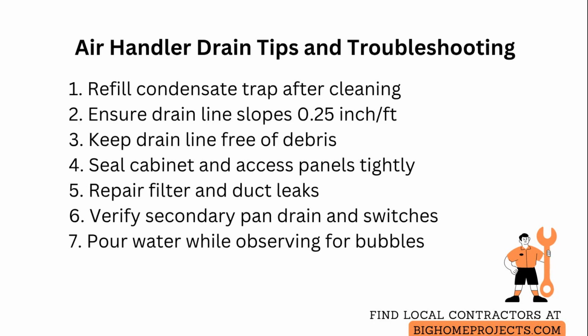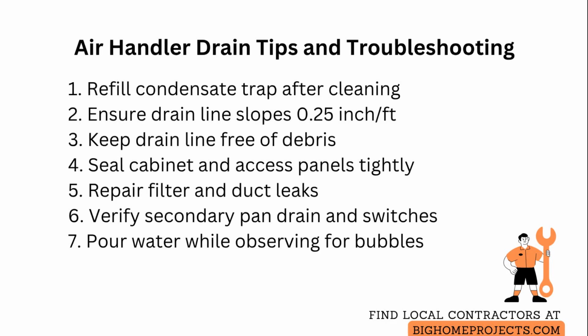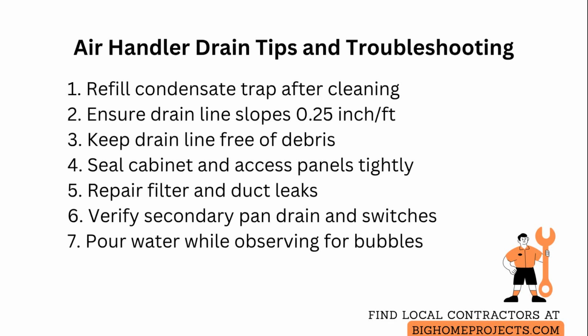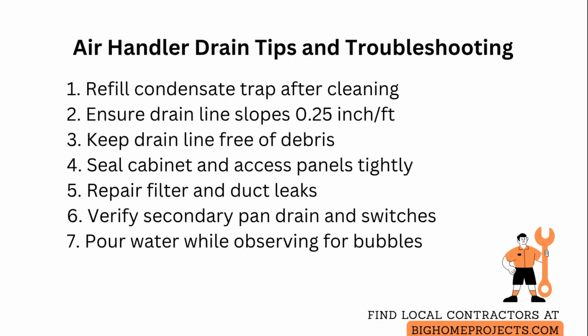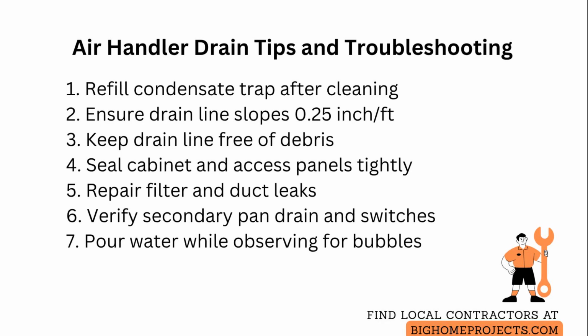Confirm the air handler, cabinet, and access panel seat tightly and that any filter or duct leaks are repaired, because uncontrolled air paths change internal pressures and encourage siphoning through the trap. If a secondary drain pan is present, make sure its drain is unobstructed and that overflow switches are correctly positioned to cut power before water bridges seals.